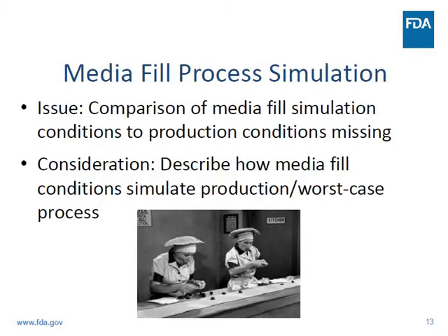Another validation study that often leads to deficiencies is the media fill process simulation. Here we really need to understand how your media fill simulation simulates your aseptic process. And we want to have a detailed description of both, so we can compare your media fill simulation conditions to what you plan to do for production. So describe how the media fill conditions simulate production or worst case process.